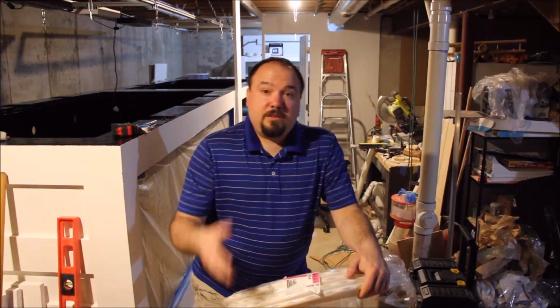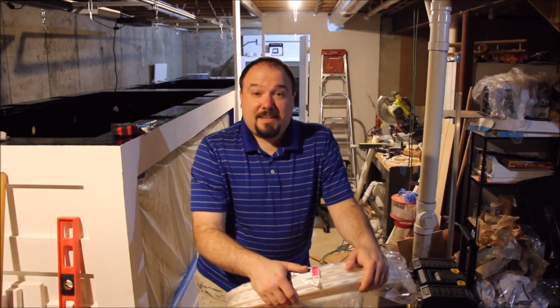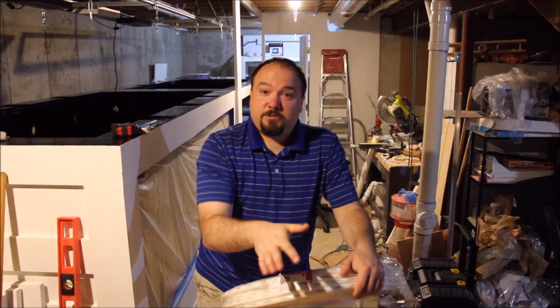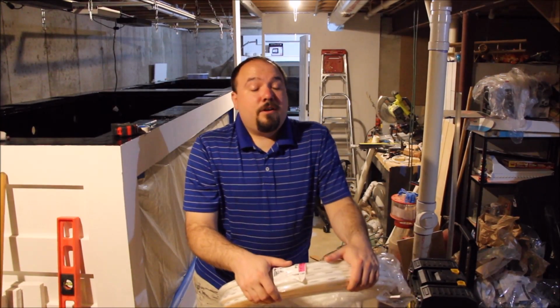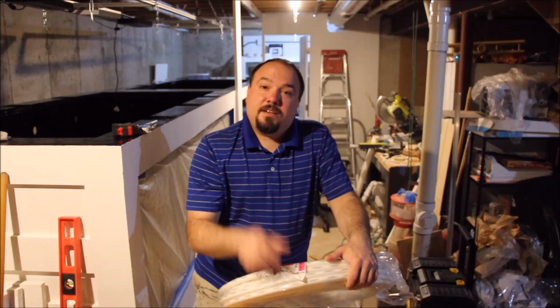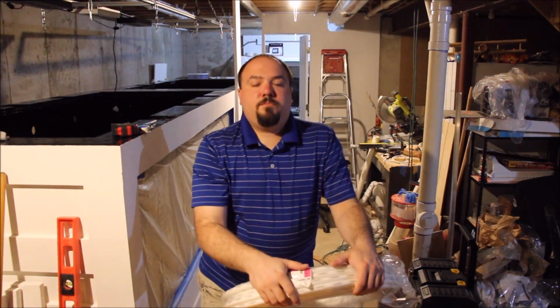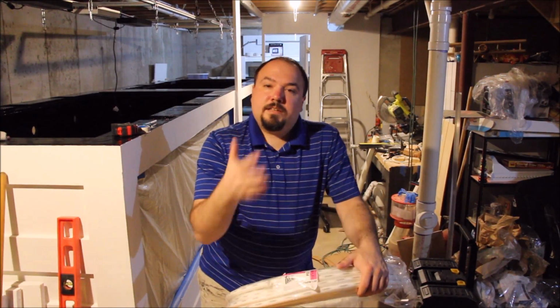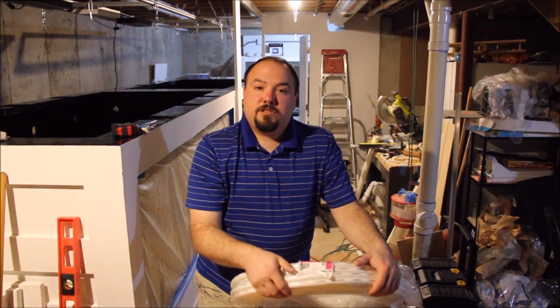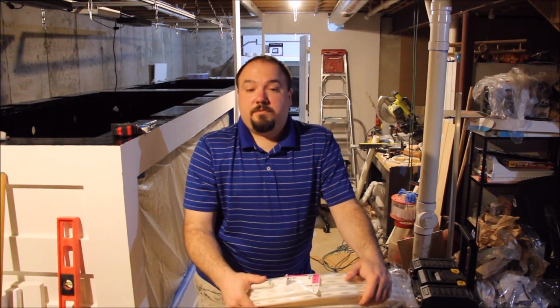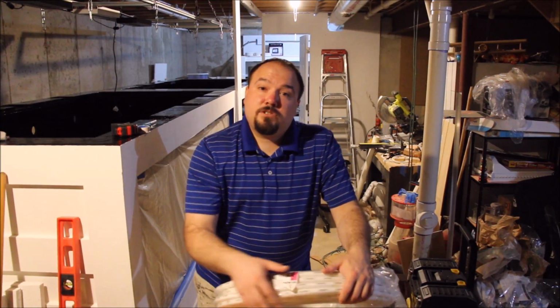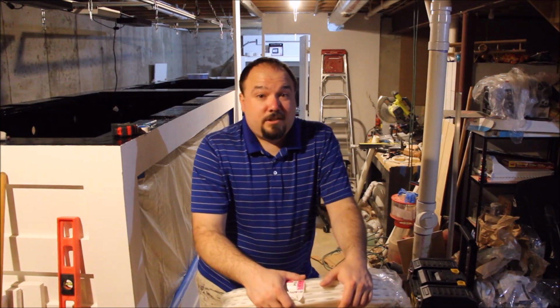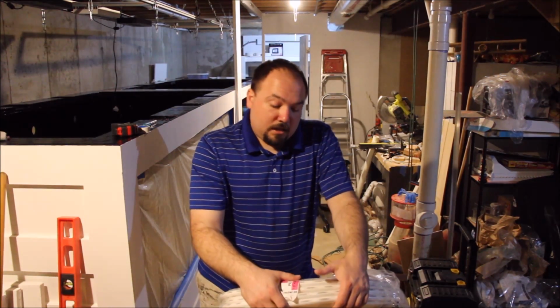Quite frankly, even my supply line is right next to the gas line for my dryer, and I don't want to use a torch near that. So we're using compression fittings to keep it simple—just need a pipe cutter to tap in, take a section out, and put the compression fittings in. I also have shut-off valves for the supply and return so I can isolate if needed. Worst case, if I have to remove a section, or in another scenario add a section for more heating, I can always cut it and use more compression fittings.